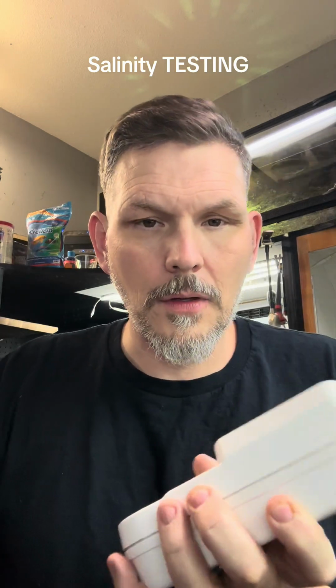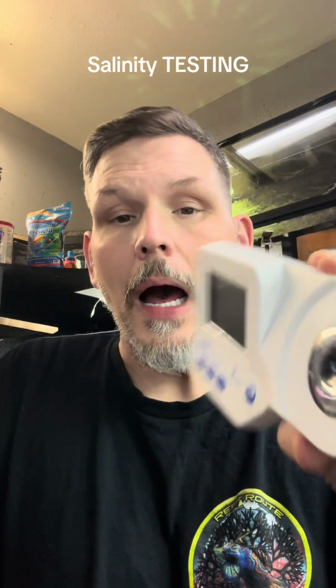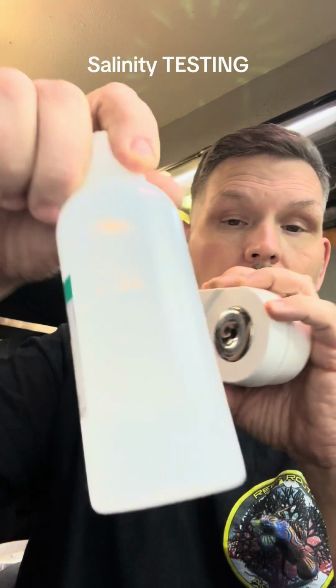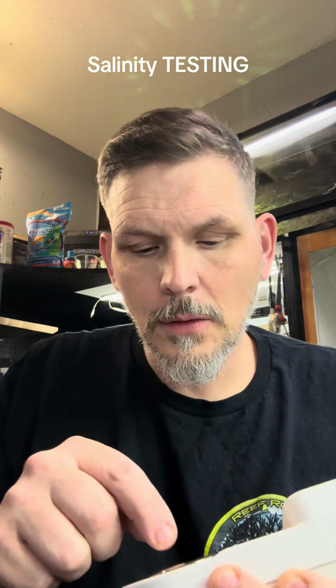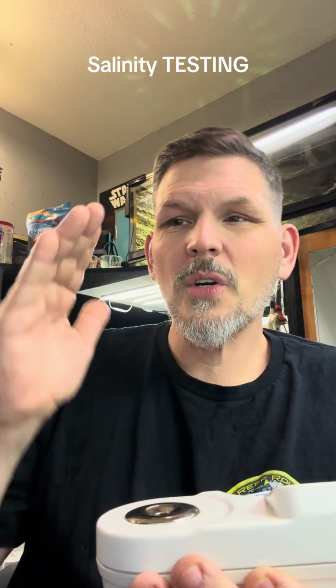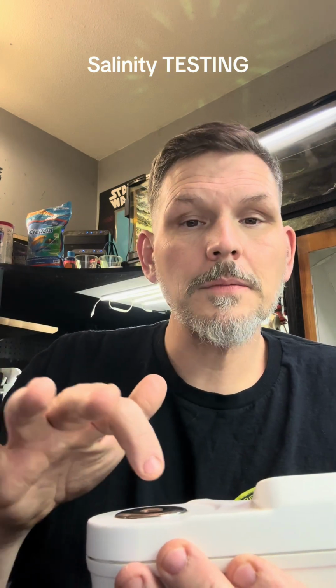The second device that we use, it's very, very handy, very, very neat, right, is we got these little handheld refractometers, okay? Whether it's Hanna, Milwaukee, you've seen this button format before, we know what's going on with this, okay? This gets zeroed out utilizing clean deionized water, okay? And from that standpoint, very, very accurate. All right. The problem with these is that these little guys have that prism in there and everything else, and in an area where it's well lit, could end up messing up what it's actually reading. Okay.